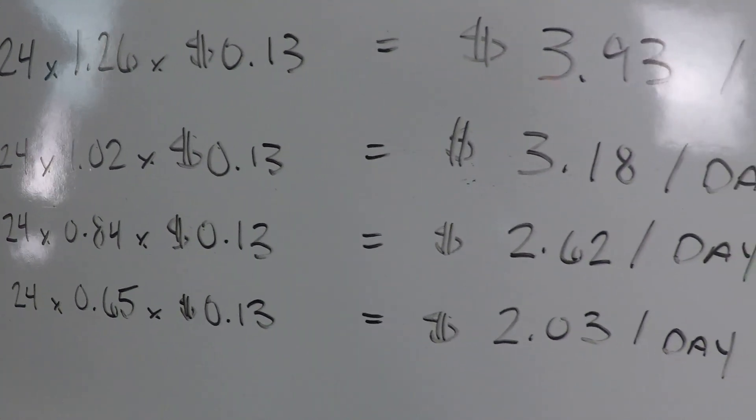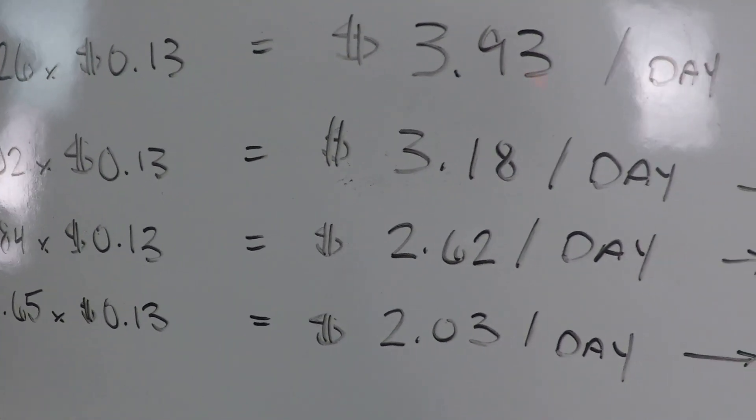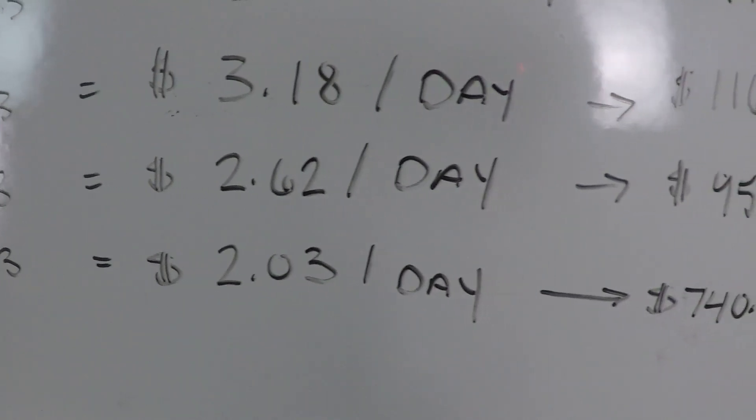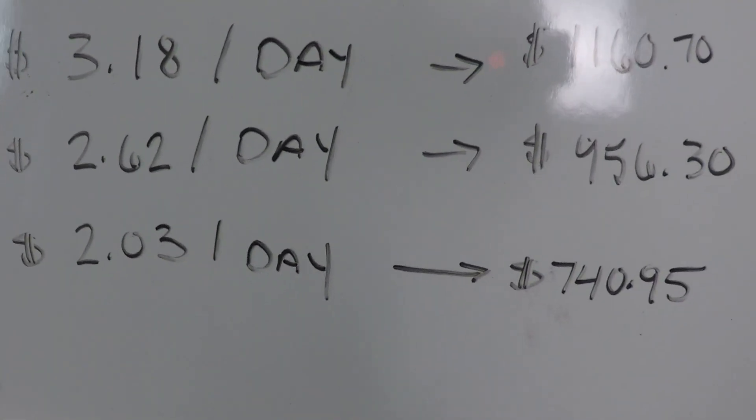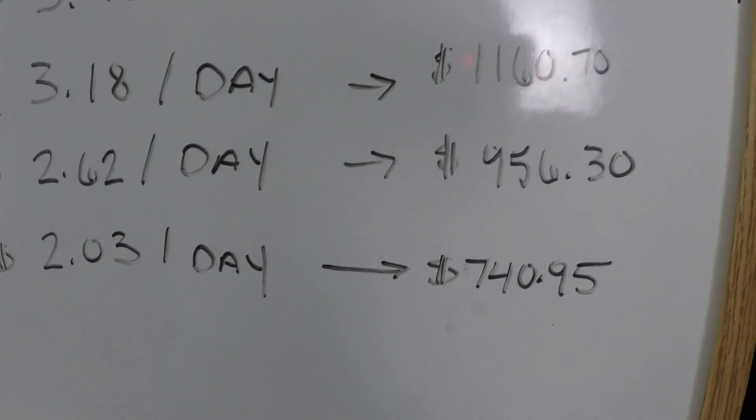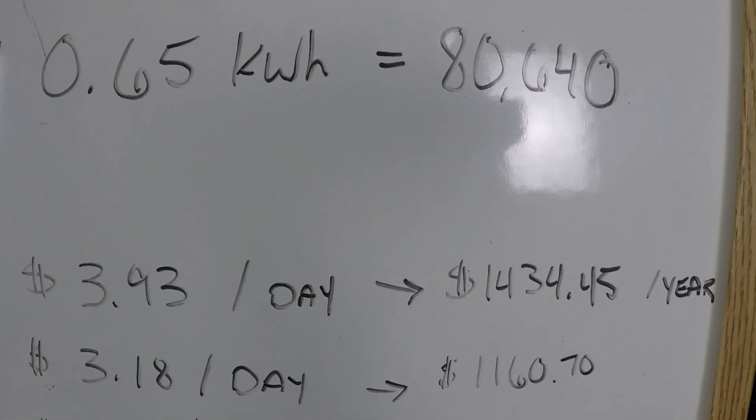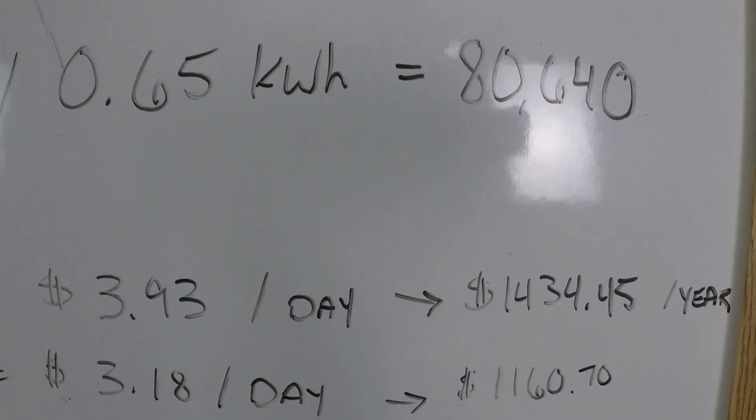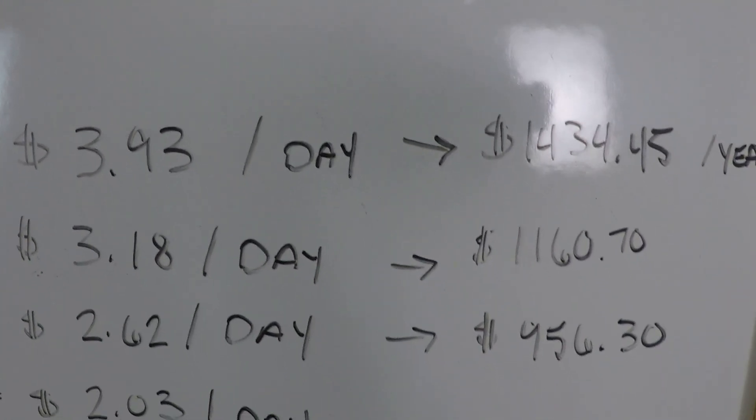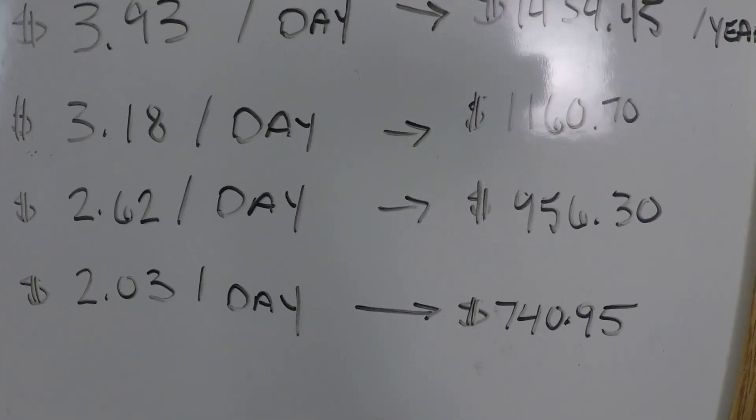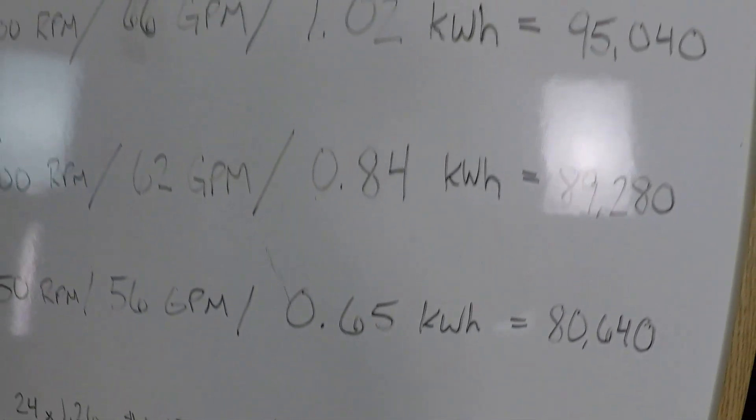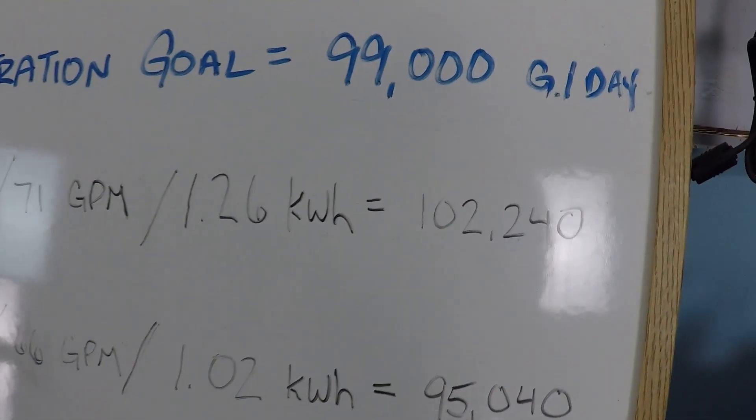Look at that bottom equation, 24 times 0.65 kilowatts times 0.13, and that's the price per kilowatt hour nationwide average, $2.03 per day, almost $741. But that's down from the 1434, that's almost half. You've cut the operational cost in half by going from 3450 to 2750.